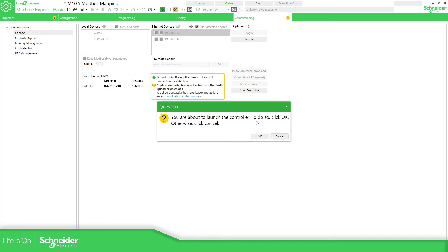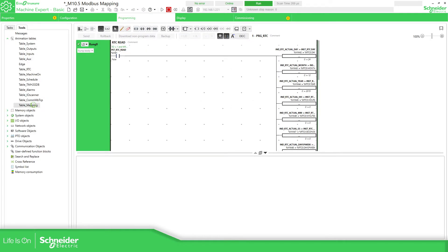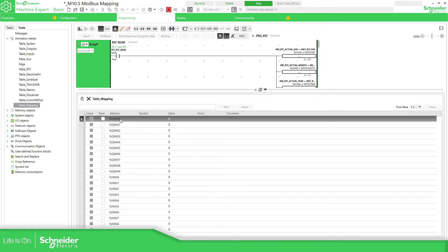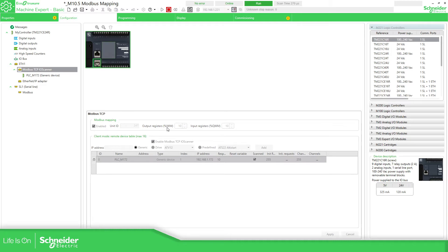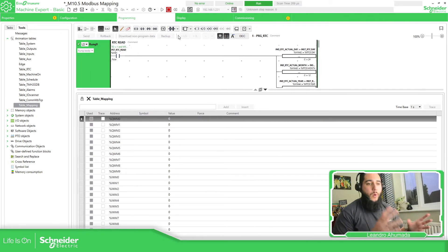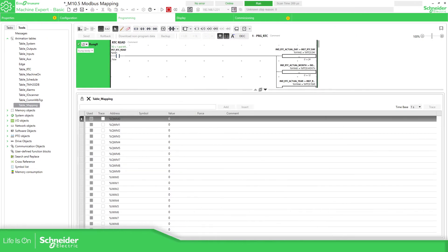We are now online and running. I have already configured a table here where I have %QWM0 through %QWM9. I also have the input registers and output registers — output register QWM and input register IWM. This is already configured on the M221. Now we need to configure the other device to read and write information to this specific area, so let's go to EcoStruxure Machine Expert.